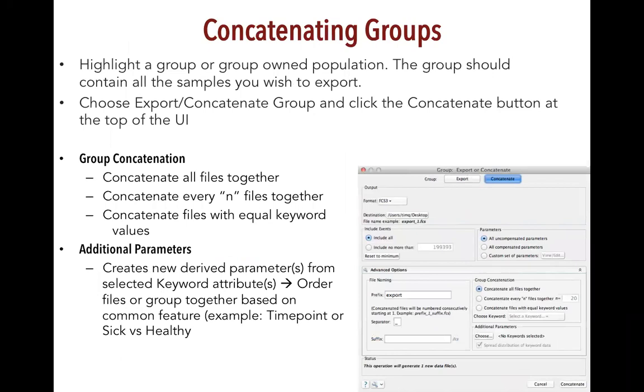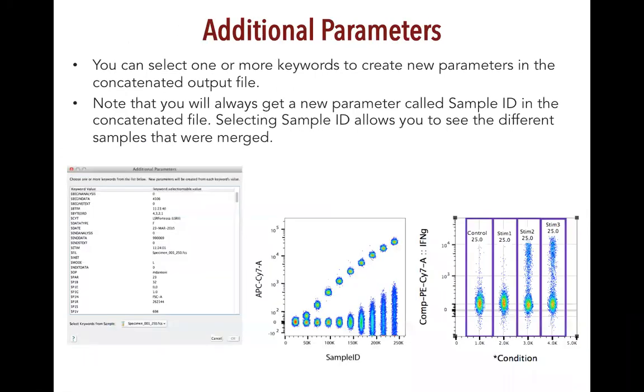Concatenate groups works the same way, except you highlight the group instead of individual files. For example, here is a merged concatenated file where I ran beads stained with an APC-Cy7 antibody-conjugated fluorochrome, titrating up the voltage on the photomultiplier tube detector for APC-Cy7. As I increase the voltage, separation increases between the negative and positive fraction. After a certain point, you get spreading due to increased PMT voltage without better separation — there's a sweet spot you can visualize easily with a concatenated file output.